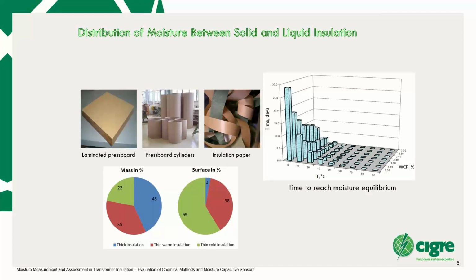Moisture is like a phantom. That's why it's very difficult to determine it definitively, because it moves from one place—from solid insulation into the oil and vice versa—depending on different factors: temperature, the thickness of the insulation, and the amount of moisture. That's why the question of moisture is very often controversially discussed. But one thing is definitive and clear: if we have moisture, we have a problem.